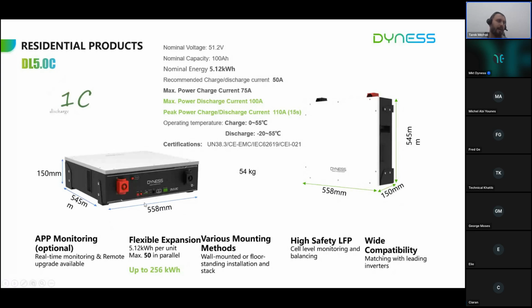As we said before, this battery can be expanded up to 50 pieces in parallel, for a capacity of 256 kilowatt hours. So this item can be used for small commercial projects up to 256 kilowatt hour. And like most of our products, this product can be installed floor mounted or wall mounted; we'll check all. For sure, it has a wide compatibility range and is compatible with more than 30 brands of inverters.